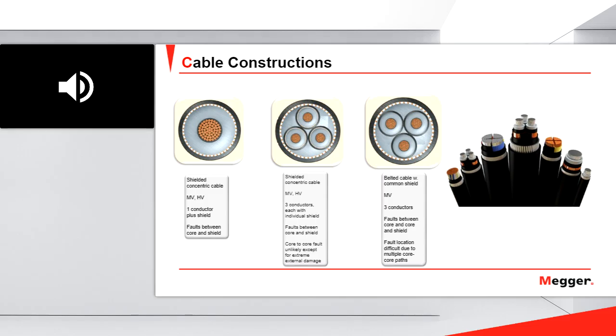And in the center, we have a three-phase cable. If you look at this three-phase cable, you will see that each one of the phases has its individual concentric. So the way to find a fault in the first two cables is pretty much the same, because when we have a fault, the fault is going to happen between the conductor and the concentric. The same for the second cable.